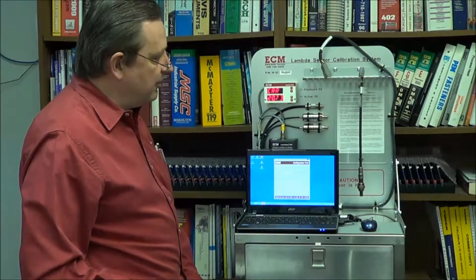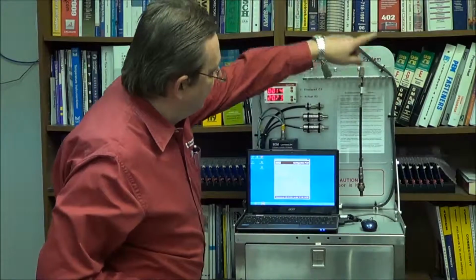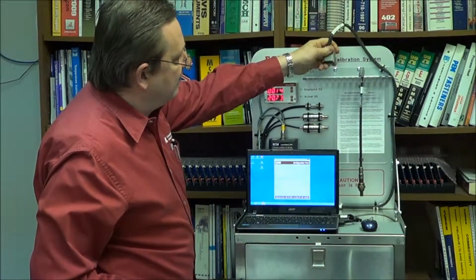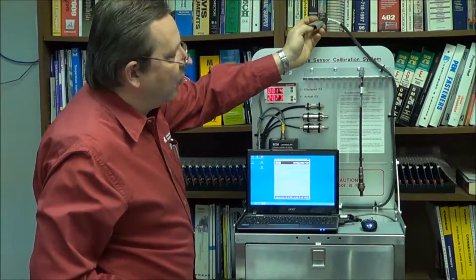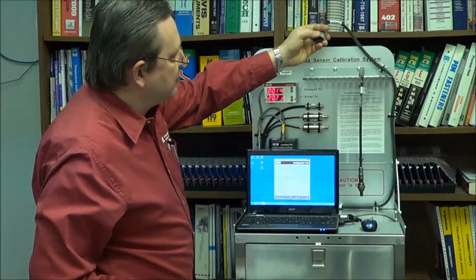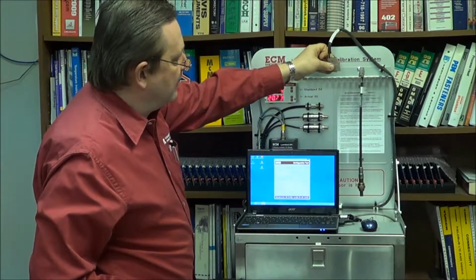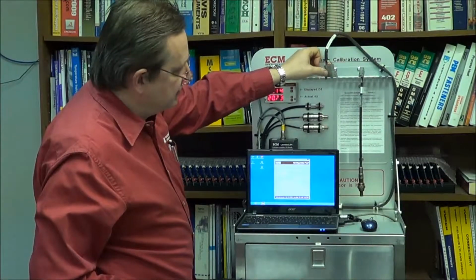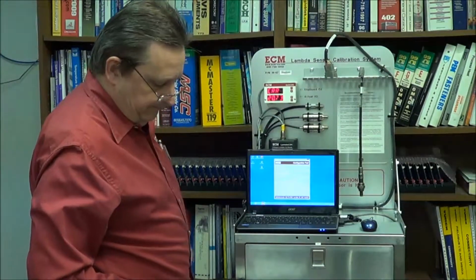Also, we recommend once a year that you replace this Lambda cable, because after repetitive insertions, you might wear the gold off the terminals and cause a voltage drop inside the connector. It's easy to replace this cable.